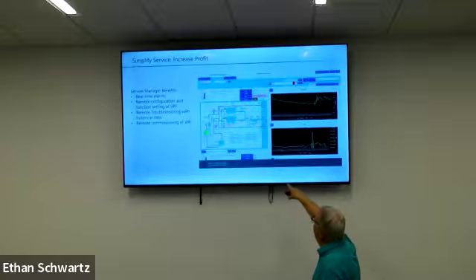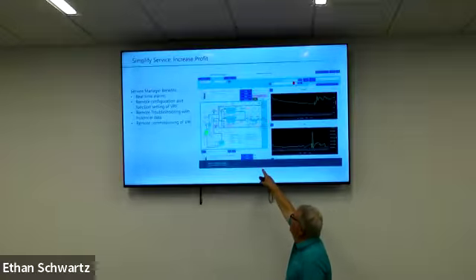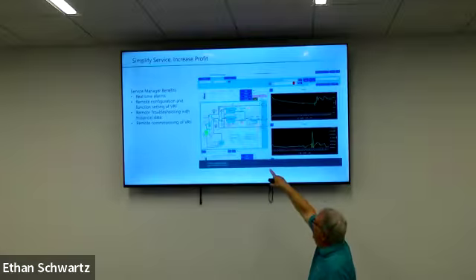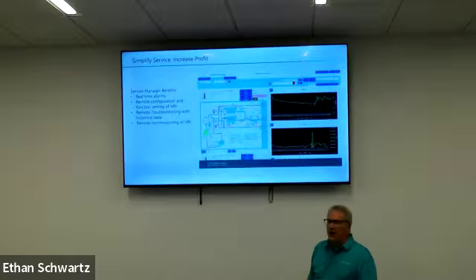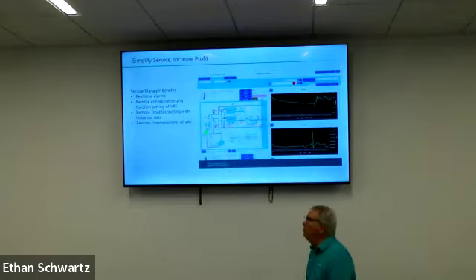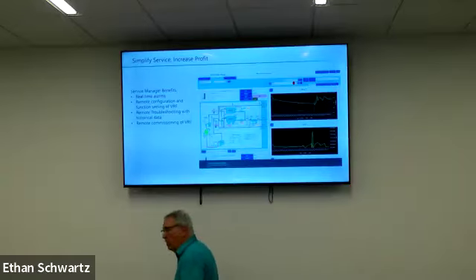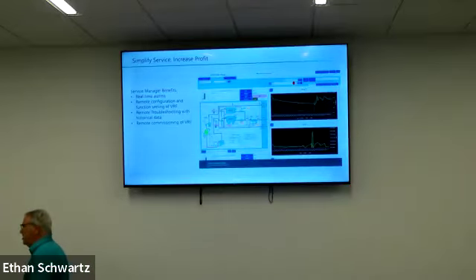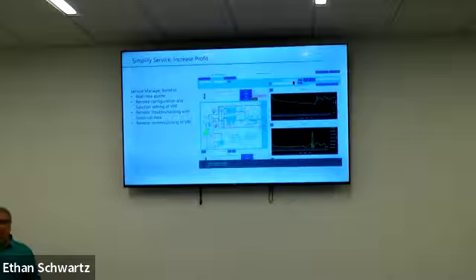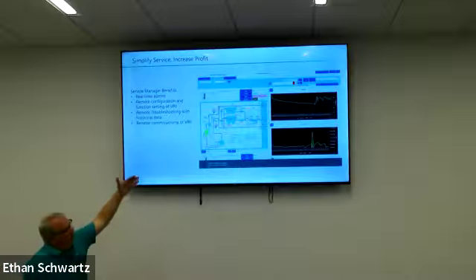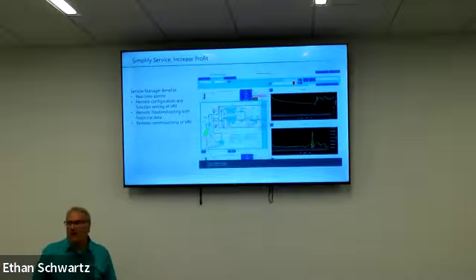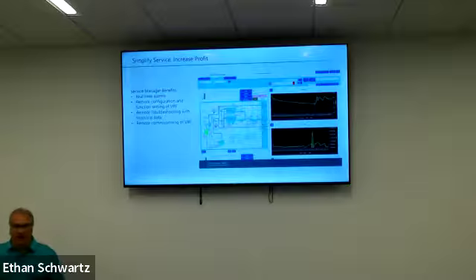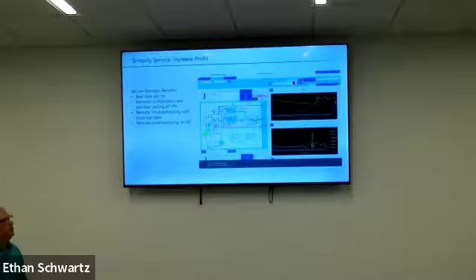What it's showing is the outdoor unit screen, and anything colored in green is on. This system is an 8-ton system. It is a VR2, and we can go around the piping. It's diagrammatic, so the contractor can look at that large commercial building and see what's going on with it before he or she ever sends a truck out there to respond to that situation. Because sometimes it's just a unit that was turned off. And then if we go up and make another selection, we can see all of the indoor units, just like we would if I was standing there with the service tool hooked up to the system watching it.